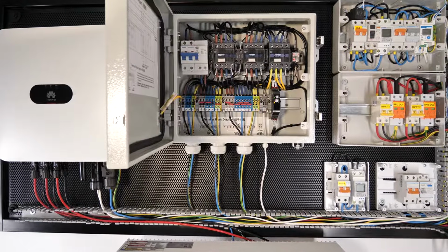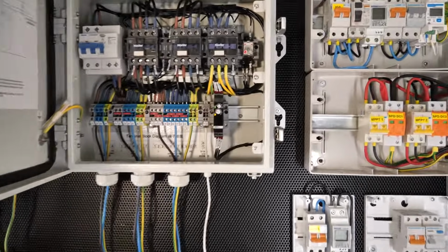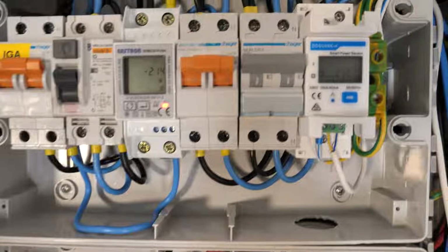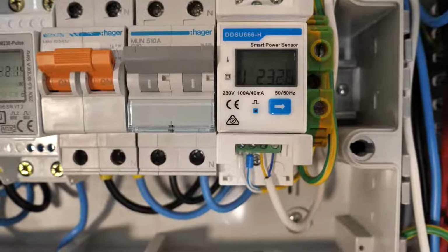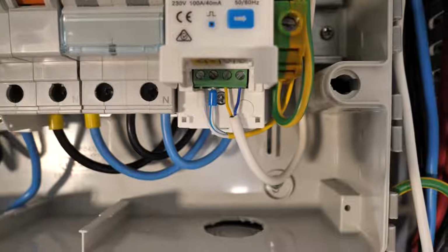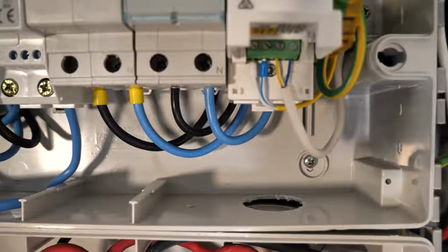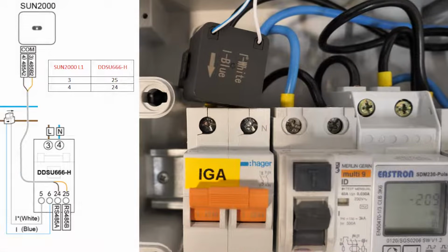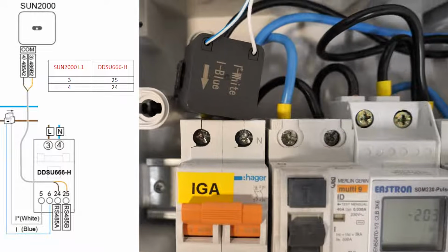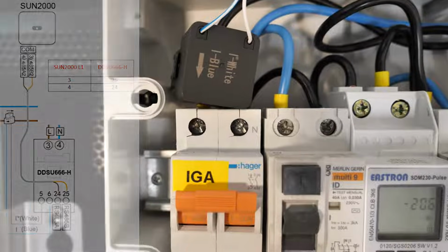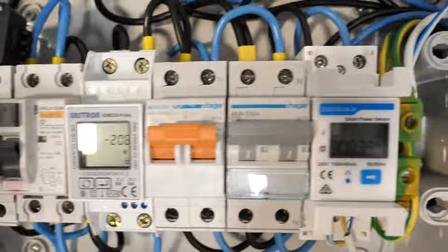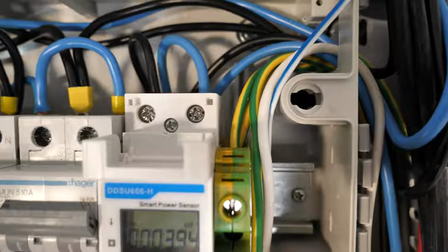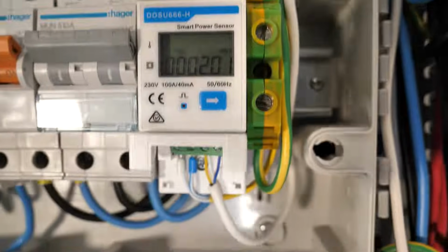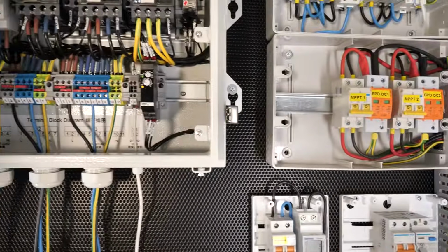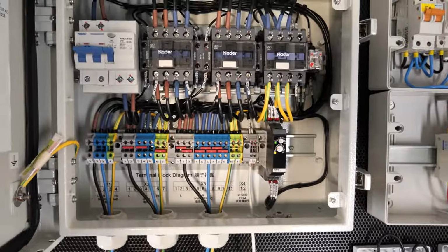Here you can see in more detail the installation: on one hand, the energy meter in this part. In the lower part you see the communication cables going towards the photovoltaic inverter, and the cables that go towards the toroidal sensor, located on the phase cable coming from the power supply. The arrow points towards the house, towards the consumption. At the top we have connected phase and neutral from the power supply, and below, the communications. Then over here we have the contactor box.